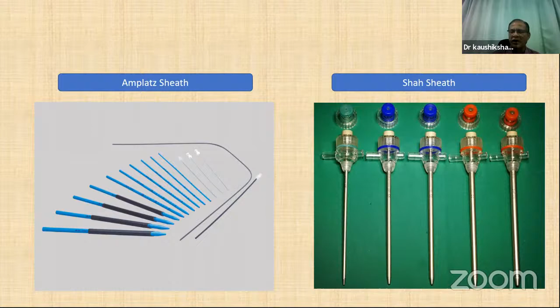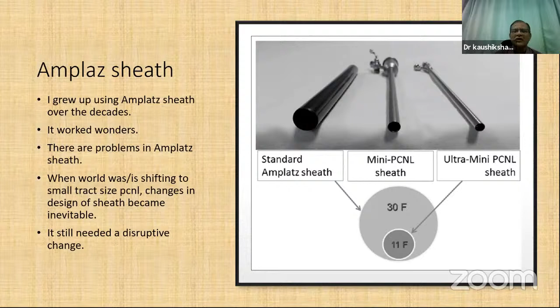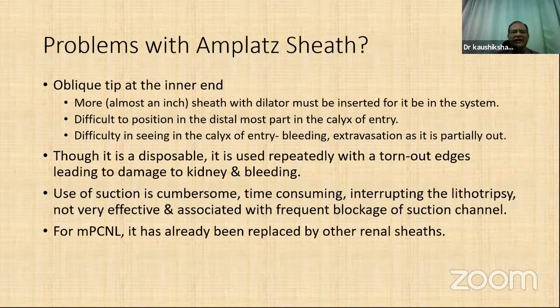I grew up using the Amplatz sheath over decades. It has worked wonders, but it has problems. As the world shifted to small tract size PCNL, the design needed to change, and it still needed a disruptive addition of suction in a sheath. The Amplatz sheath has an oblique tip, so vision at the calyx entry is difficult, and if it is pulled at the end, bleeding and extravasation occur. Though disposable, in developing countries it is reused with torn edges, damaging the kidney and causing bleeding. Suction with it is cumbersome, time consuming, interrupts lithotripsy, is not very effective, and blocks frequently. For mini PCNL it has already been replaced by other sheaths.